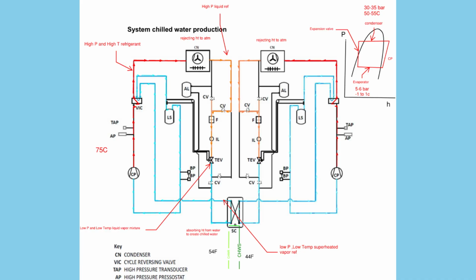5. Heat absorption, evaporator, chiller barrel. The cold refrigerant mixture enters the heat exchanger, which in this mode acts as the evaporator. Inside the heat exchanger, chilled water circulates through tubes. The refrigerant absorbs heat from the water, causing it to boil and turn into vapor. The water leaves the heat exchanger cooled. This is the chilled water that goes to the building's cooling system. The refrigerant, now a low-pressure vapor, returns to the compressor, and the cycle continues.